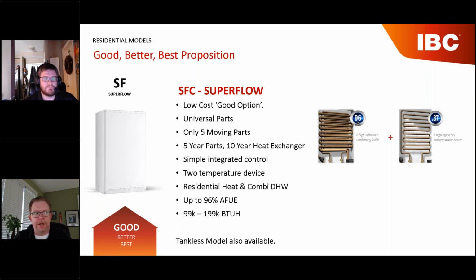That single pass design on the water side means that as you build debris, you're actually increasing the flow velocity. In a traditional heat exchanger, you've got a lot of little fingers running the length, not just one tube that goes the whole way. When you plug one of those, the water goes to the path of least resistance. With this one, there's only one flow path, so you can't go path of least resistance. You increase that velocity, and it pushes the sediment off it. It doesn't mean it doesn't need to be maintained and cleaned, but it's a very bulletproof way to maintain this unit.